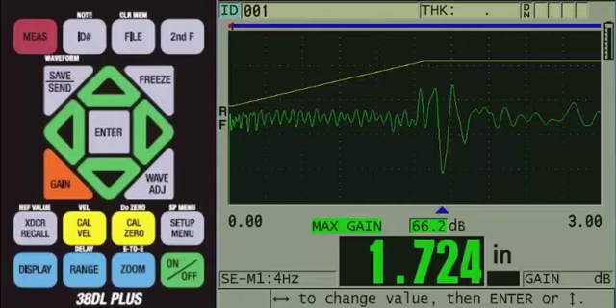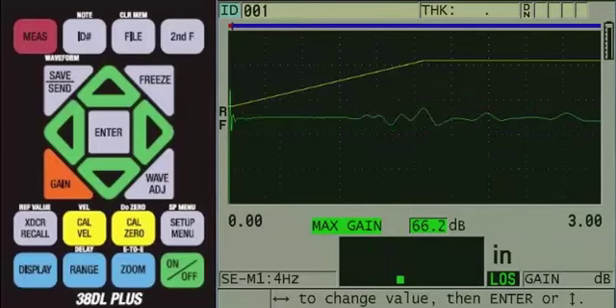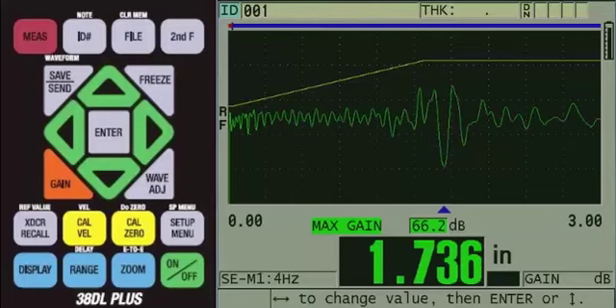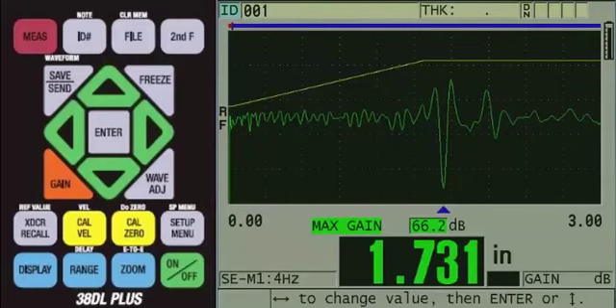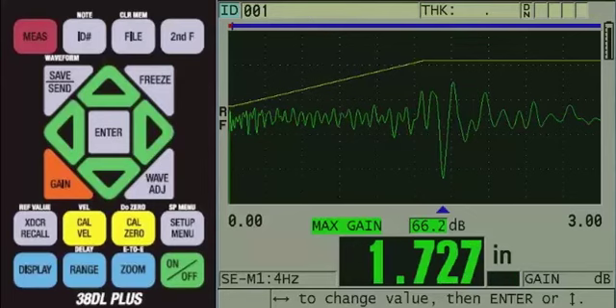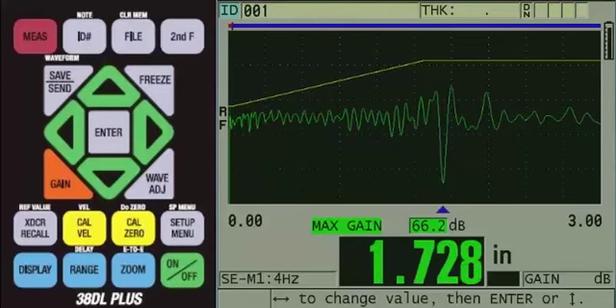At this point, it is a good idea to check multiple spots on the sample to make sure no further adjustments are needed. If you can successfully measure the back wall echo on multiple spots on the sample, then no further adjustments are needed, and we can go ahead and calibrate. For best accuracy, we would calibrate using 2 samples of the same material with known thicknesses representing our minimum and maximum thickness. For this demo, we only have 1 sample, so we will perform a single-point velocity calibration.